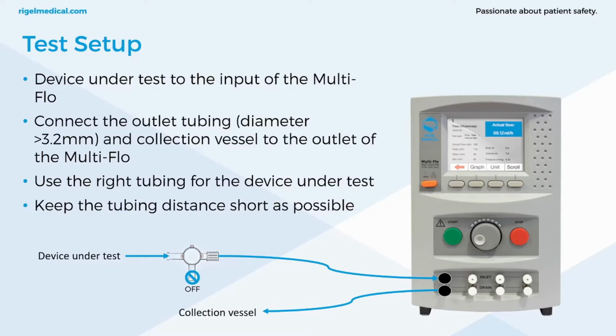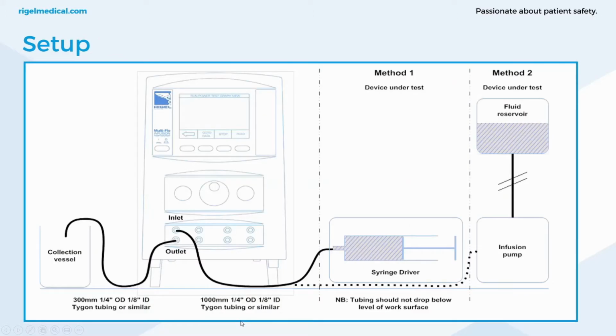So we connect the outlet tubing and collection vessel to the outlet of the Multi-Flo. We use the right tubing for the device under test, and we keep the tubing distance as short as possible. And here we see the valve is now just going straight from the device under test to the input of the Multi-Flo and to the collection vessel. And this is just a better representation of how this is carried out. So depending on what you're using, so we've got a volumetric infusion pump. The inlet would go through here via the T-piece or the 3-way valve into the inlet, and then the outlet will go straight to the collection vessel. Pretty simple. And with the syringe driver, it's the same setup.